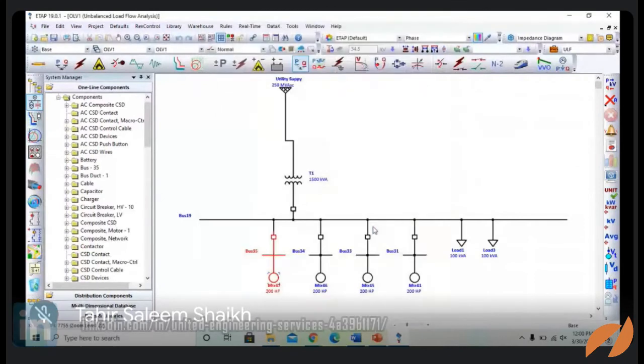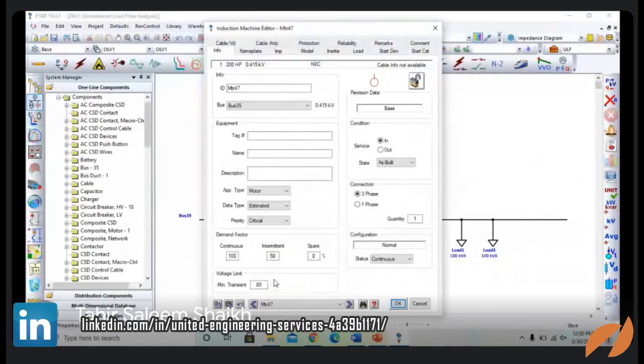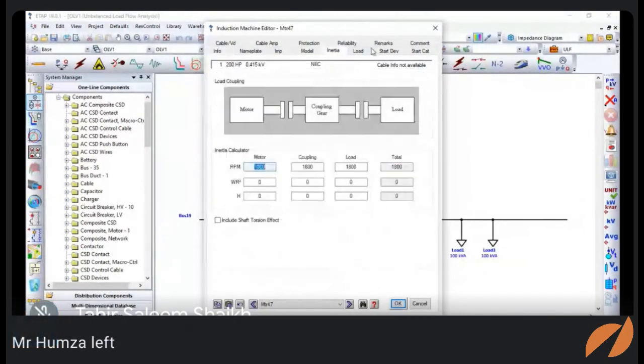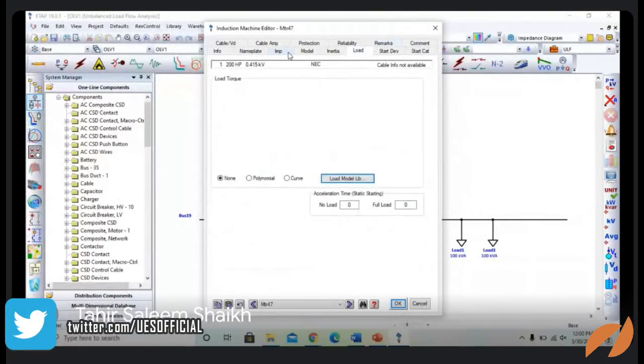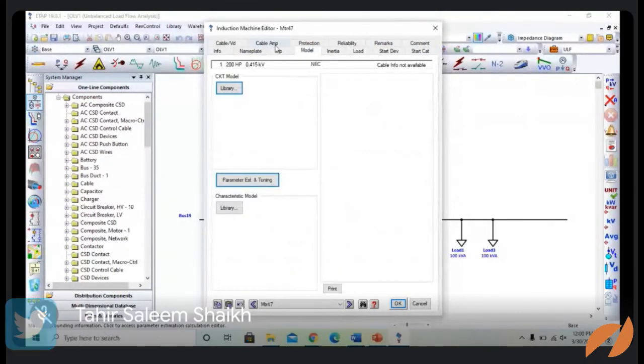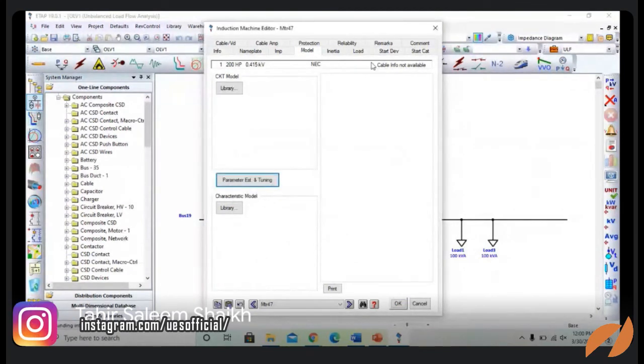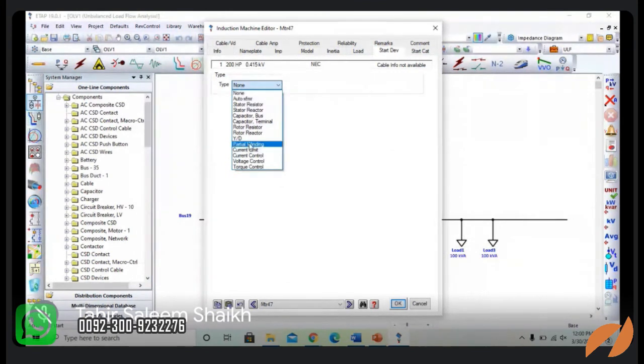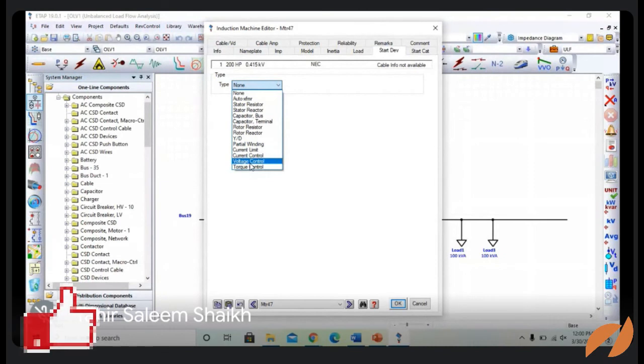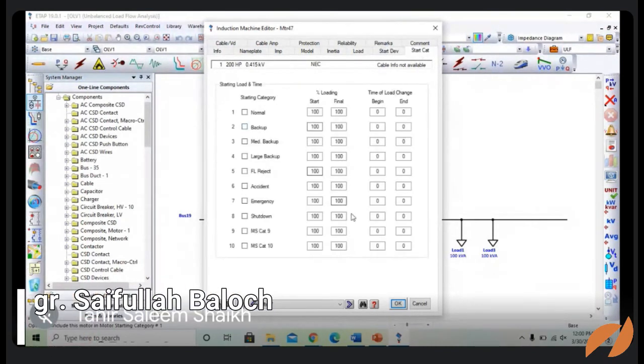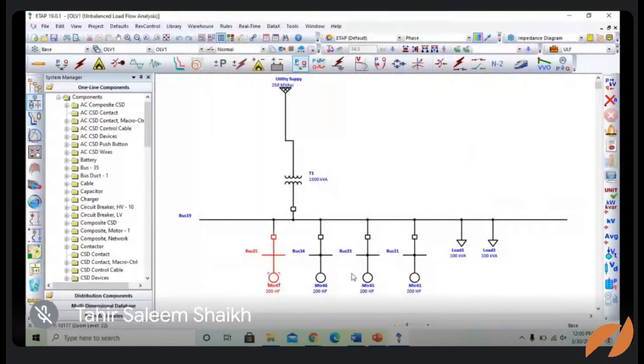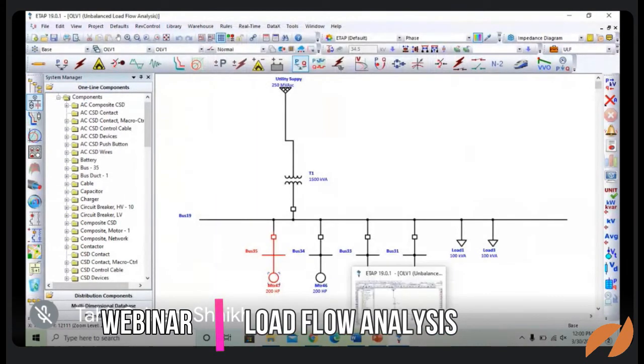Here you also have different options: inertia, load of the motor, model of the motor, cable, and inertia of the secondary device. For the secondary device, there is the starting drive. If you want to add any starting device like a stator resistor or any controlling device, star delta, whatever you want to put. So these are the user friendliness features of ETAP.